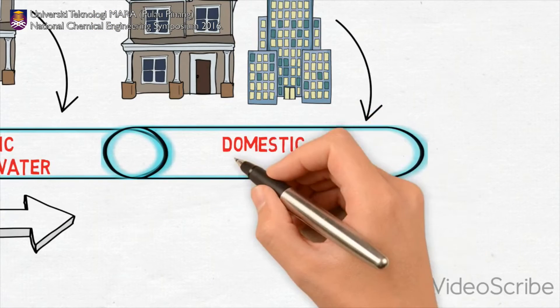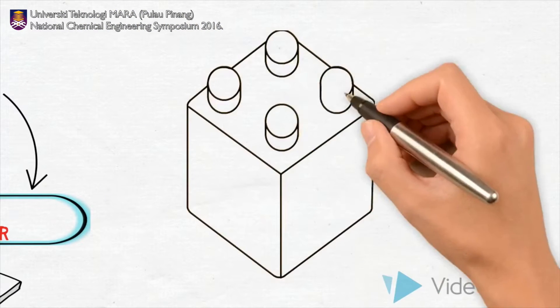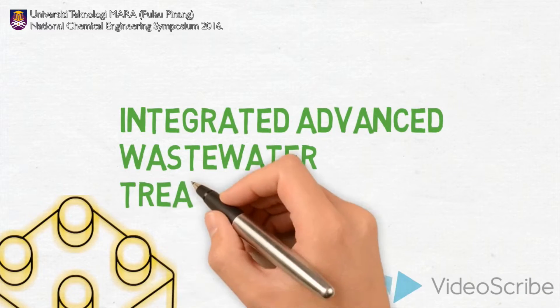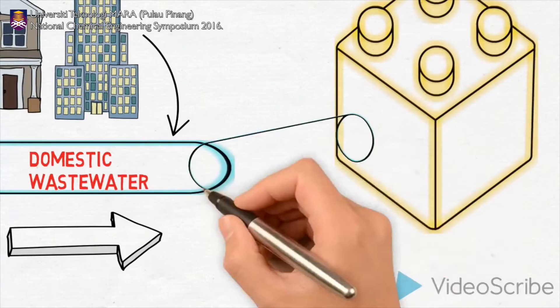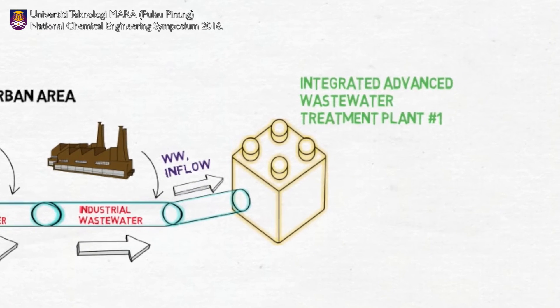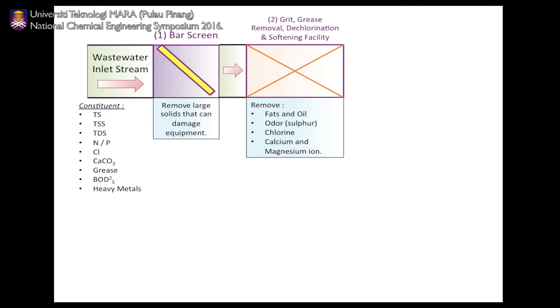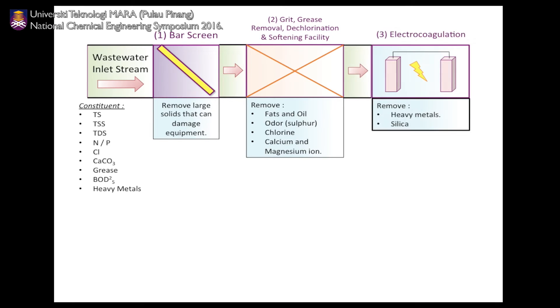This solution will only require the current wastewater treatment plant to modify its process flow and operations to suit this new process system, thus reducing setup costs. Upon collecting the wastewater from the urban area, it will directly enter the facility, where it will go through grease and grit removal and the dechlorination facility to remove critical wastewater constituents like oil, fats, and chlorine. The wastewater will also be treated using eliminators made from inorganic compounds, then undergo electrocoagulation to remove silica, heavy metals, and other contaminants that might affect industrial equipment efficiency.